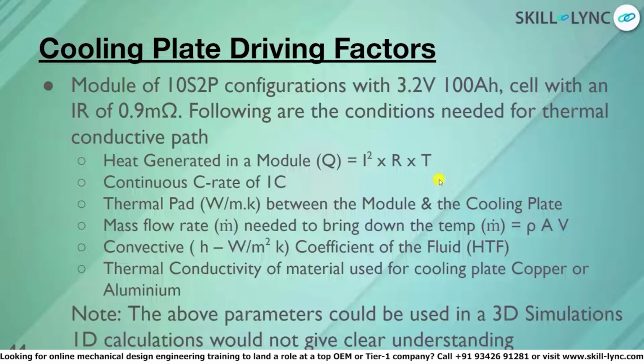Then what we need to assess is that the thermal pad has to be there between the module and the cooling plate. What is the flow rate of the fluid which is being flown? And from that we need to derive rho A V, which is dependent on the hose of the cooling pipe. And then we need to consider the convective coefficient of the heat transfer fluid, which is a function of velocity, density of the fluid, temperature, etc. And we also need to consider the cold plate material properties.